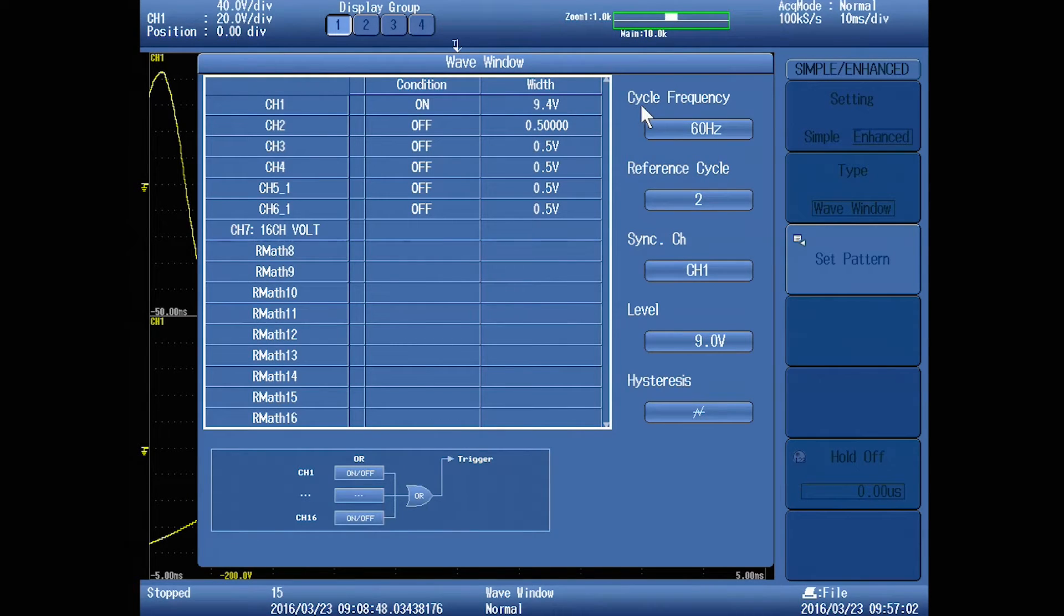You need to tell the wave window trigger the cycle frequency, in our case 60 hertz, and the reference cycle. That means it's going to use two full sine waves as the reference template. And again, we're telling it to watch only channel one. That's the wave window trigger settings.